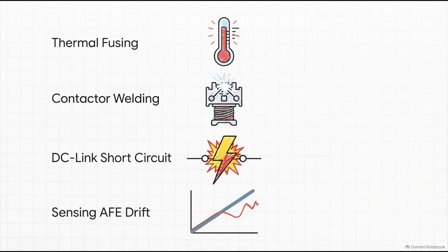Second is contactor welding. Sometimes the main relay is already physically stuck or welded shut from a previous high-current spark. So when the system tries to pre-charge, the energy violently bypasses the resistor entirely. Third, we have DC link short circuits. This is a brutal hardware breakdown, like a semiconductor failing or a motor winding shorting directly to the ground. The energy pours straight into that short, and the capacitor never actually charges. And finally, sensing AFE drift. This happens when moisture or extreme heat causes the sensors to misread the voltage. It essentially tricks the computer into thinking the pre-charge failed when it actually hasn't.